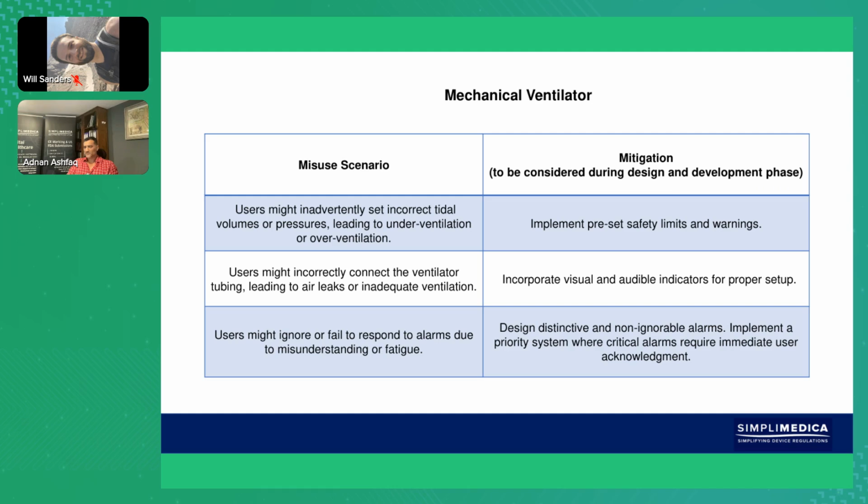Step 3, present the sterile packaging to a scrub nurse. Step 4, remove the device from within, etc., etc. So all I'm trying to do is give you a very logical way of putting down the failures that might end up coming from a user because they're incorrectly using the instructions for use, which all comes back and stems from the intended use statement.